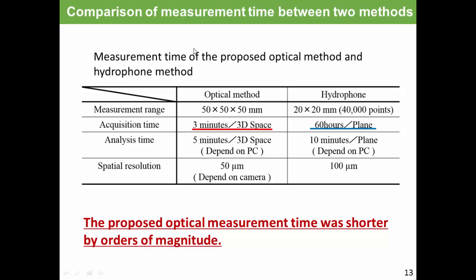Let me explain the comparison of measurement time between two methods. This table shows measurement time of two methods. For acquisition time, the optical measurement for a 3D space took approximately 3 minutes. Hydrophone measurement for a plane took more than 60 hours. So, the proposed optical measurement time was shorter by orders of magnitude.